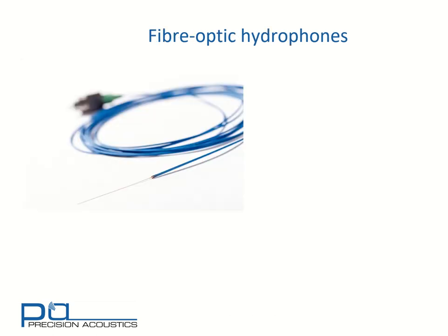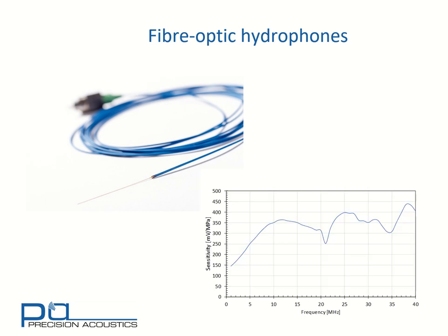Fiber optic hydrophones, like needles, also have diffractive resonance behaviour. But because they're very much smaller, these diffractive effects don't tend to appear until much higher in frequency. In the case of this hydrophone, we're starting to see those effects from about 19 to 20 MHz up to 40 MHz. Below about 10 MHz for the fibre optic hydrophone, the response is pretty linear.